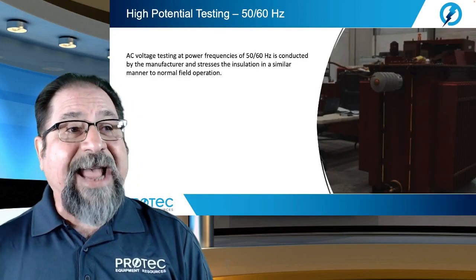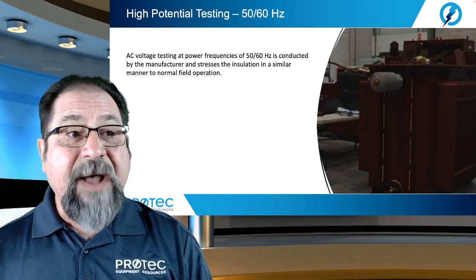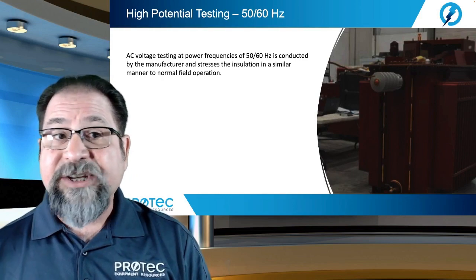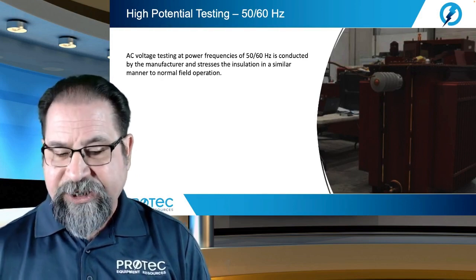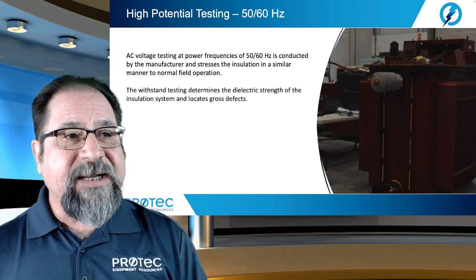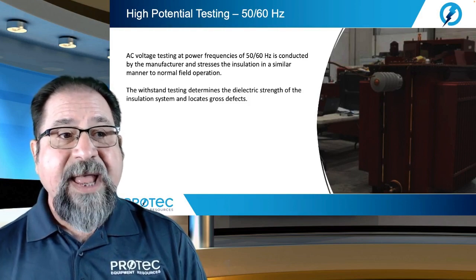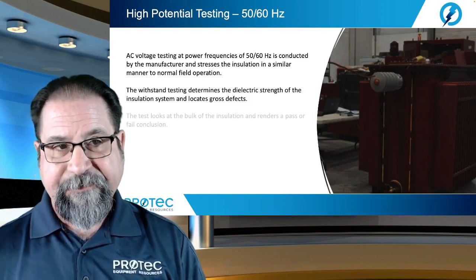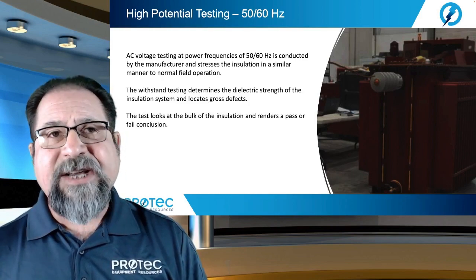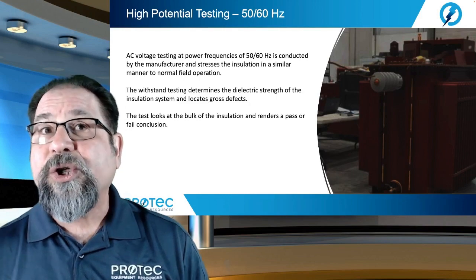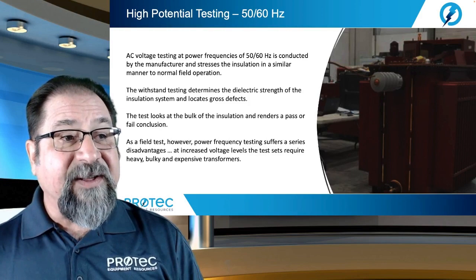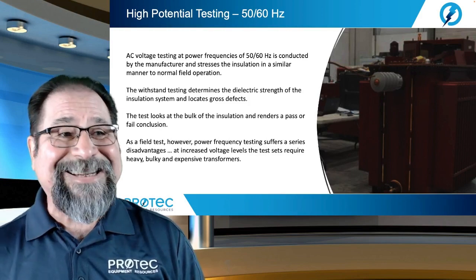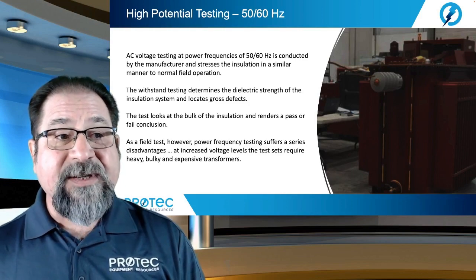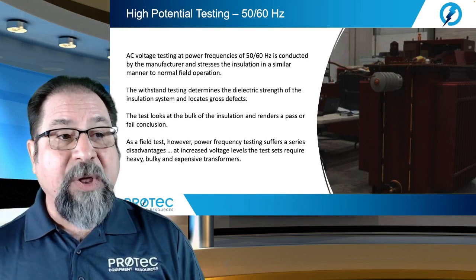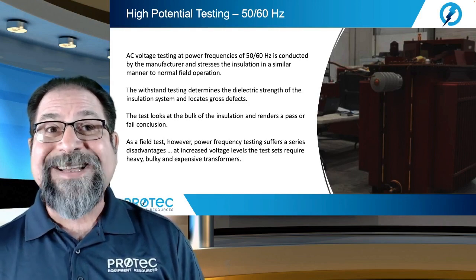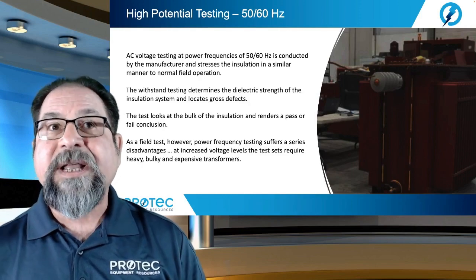Now, AC voltage testing at power frequencies of 50 to 60 hertz is conducted by manufacturers, and it stresses the insulation in a very similar manner to basic field operation. The withstand testing determines the dielectric strength of the insulating system and locates gross defects. The test looks at the bulk of the insulation and renders a simple pass-fail conclusion. As a field test, however, power frequency testing suffers a serious disadvantage. At increased voltage levels, the test set requires very heavy, bulky, and expensive transformers in order to produce the necessary volt amps, or VA, required to energize the cable.